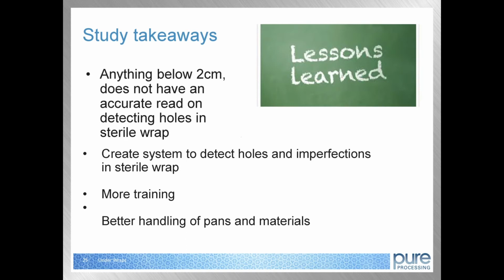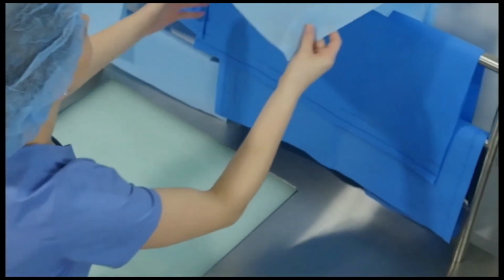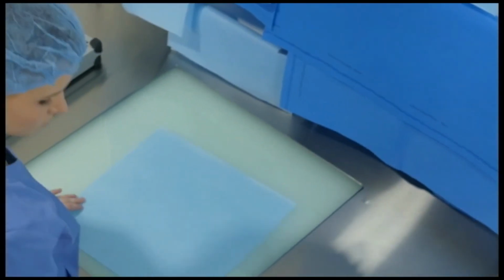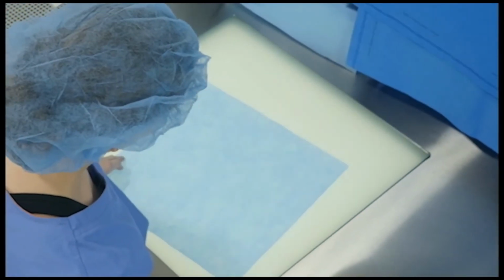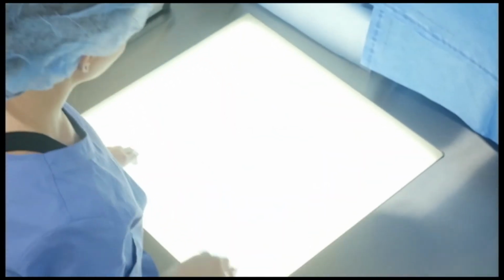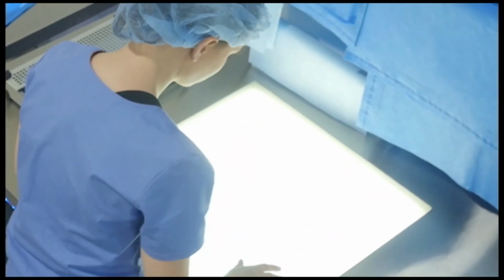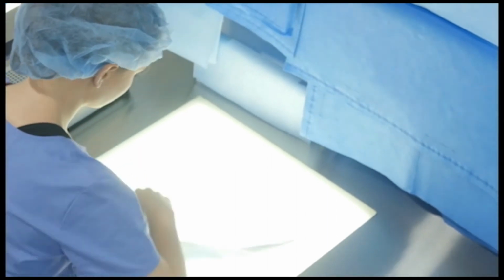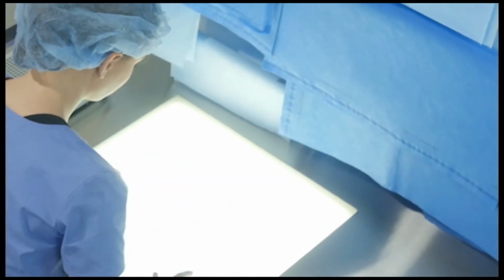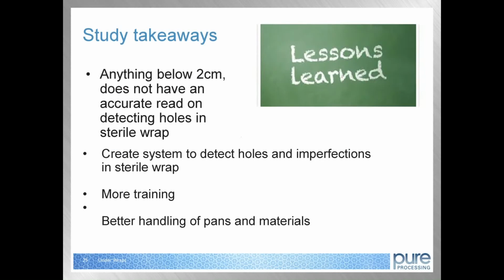So the first thing we can do, in the first line of defense, is sterile processing. In sterile processing, being the ones that wrap the pans, we can have a system put together for finding imperfections, defects, and holes in sterile wrap. What we need to do is come up with a system where we can be more adequate at finding holes below 2 centimeters and a little bit more efficient and accurate with holes between 2 centimeters and 6 centimeters. Because what we really want is, between 80 and 90% of the time, to know that we have detected or found holes or defects.